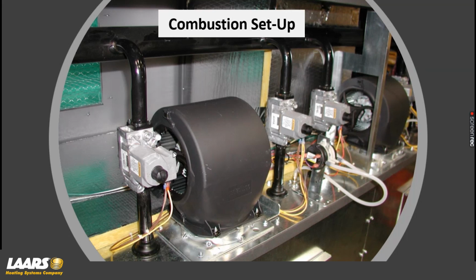Also, once you get a piece of equipment running with all valves operating, you want to double check your incoming gas pressure. For example, maybe I have 7 inches of incoming static gas pressure. Now I turn on the boiler, adjust each gas valve, and go to full fire. I want to make sure that it doesn't drop below 4 inches, okay?